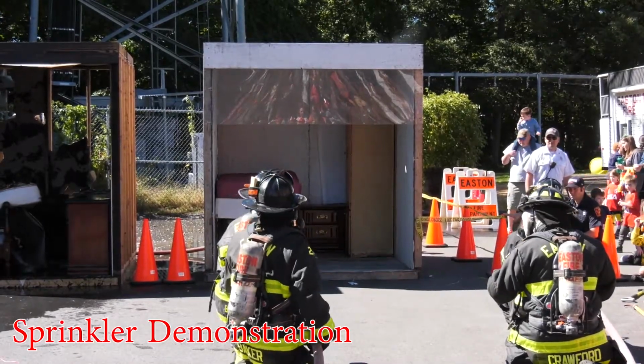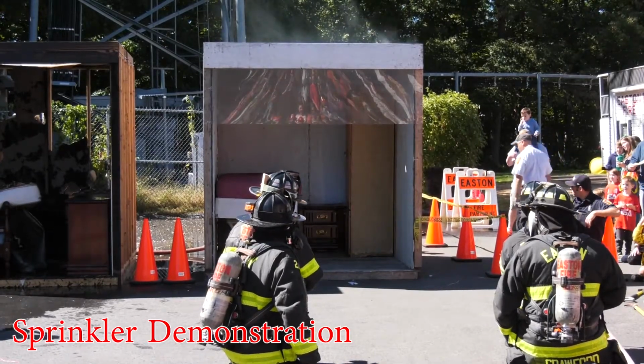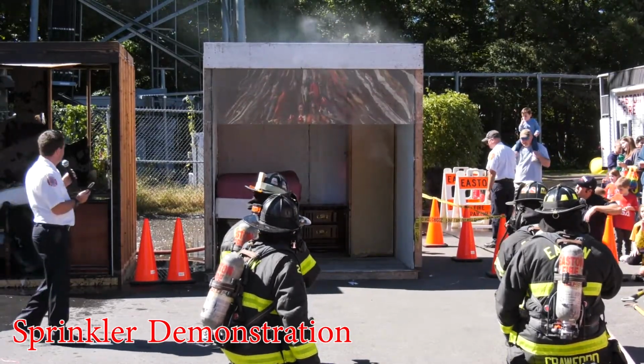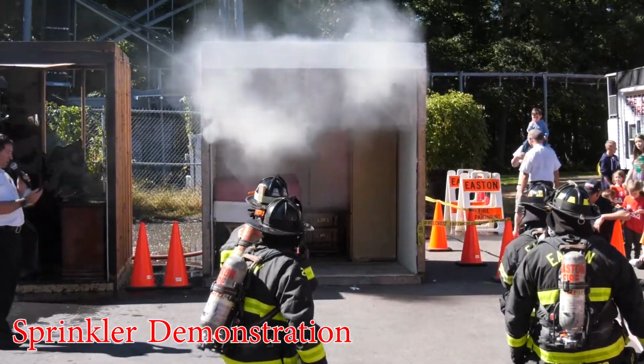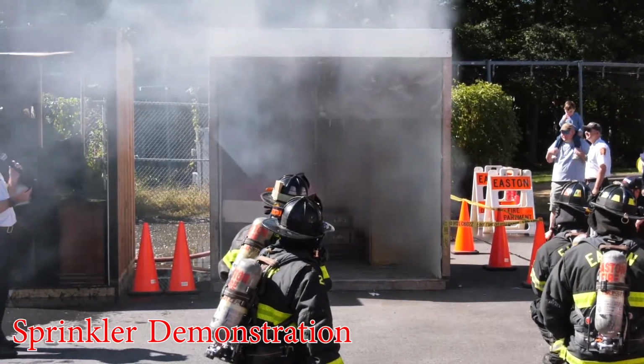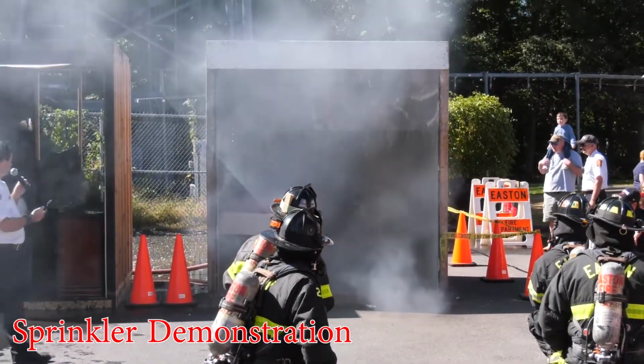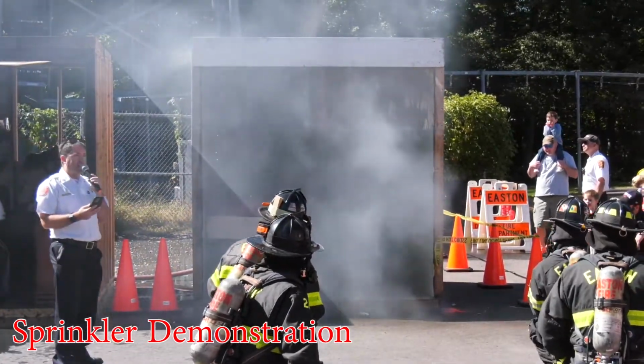Okay, we're lit. Let's see how it goes. The time's ticking. We had 17 seconds on the last smoke detector. Let's see what this one does. Here we go. There's the smoke detector. 14 seconds. And at 18 seconds, that sprinkler head just popped. And we're going to let that go, because that's going to go until we get there to finish the job.